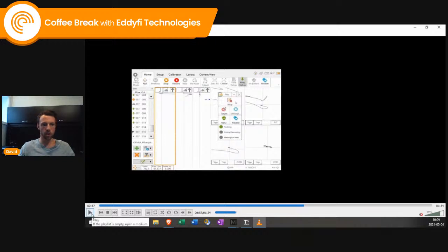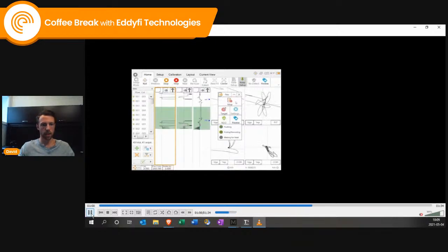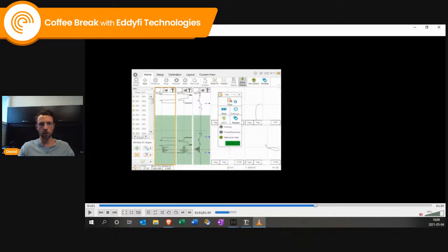So this is data that was acquired with the manual sequence, and I will stop it here. So after an acquisition, you see that the data on the screen is displayed at the top. Sorry, I cannot say here. So this is the exit signal that I see. Then it waited. Then the green is that the acquisition has started. It detected the tube sheet in, then the tube sheet out, and it waited. And in the menu here, you see that I have a waiting for the next tube in green. So this is going to be my 3 seconds before I move on to the next tube. So I'll let the little video run so you can see it in action.